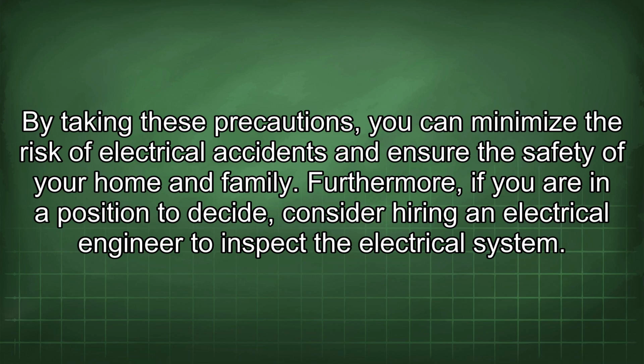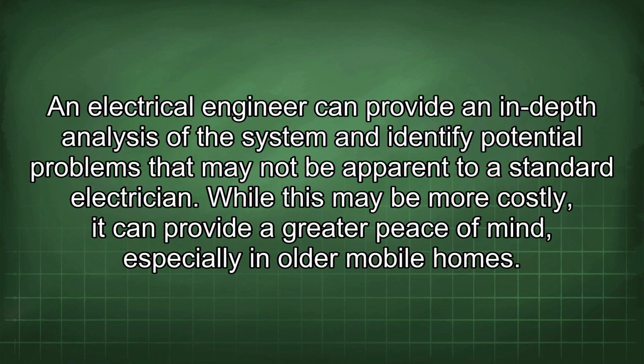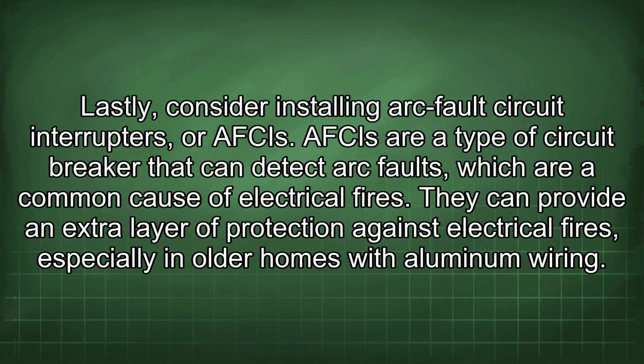Furthermore, if you are in a position to decide, consider hiring an electrical engineer to inspect the electrical system. An electrical engineer can provide an in-depth analysis of the system and identify potential problems that may not be apparent to a standard electrician. While this may be more costly, it can provide greater peace of mind, especially in older mobile homes. Lastly, consider installing arc fault circuit interrupters, or AFCIs. AFCIs are a type of circuit breaker that can detect arc faults, which are a common cause of electrical fires. They can provide an extra layer of protection against electrical fires, especially in older homes with aluminum wiring.